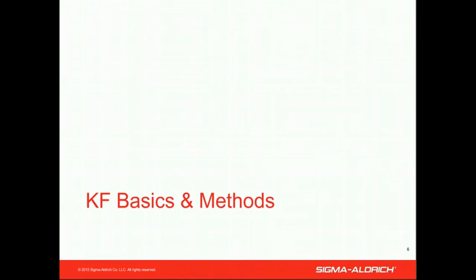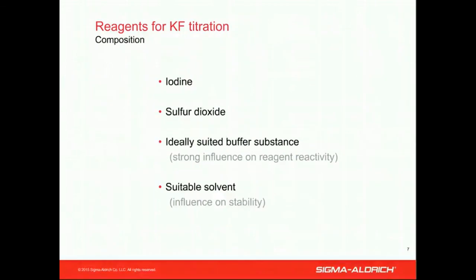Let's start with the basics of the Karl Fischer titration. I'm going to talk about the existing methods and the reagents and their composition before starting with the difficult samples. The reagents for Karl Fischer titration are composed of the substances you can see here on this slide. This was invented in 1935 by Karl Fischer, a German petrochemist who was looking for a method to determine the water content of petrochemical samples. He considered the Bunsen reaction and thought it must be possible to create a reagent and a titration method to determine that water content.